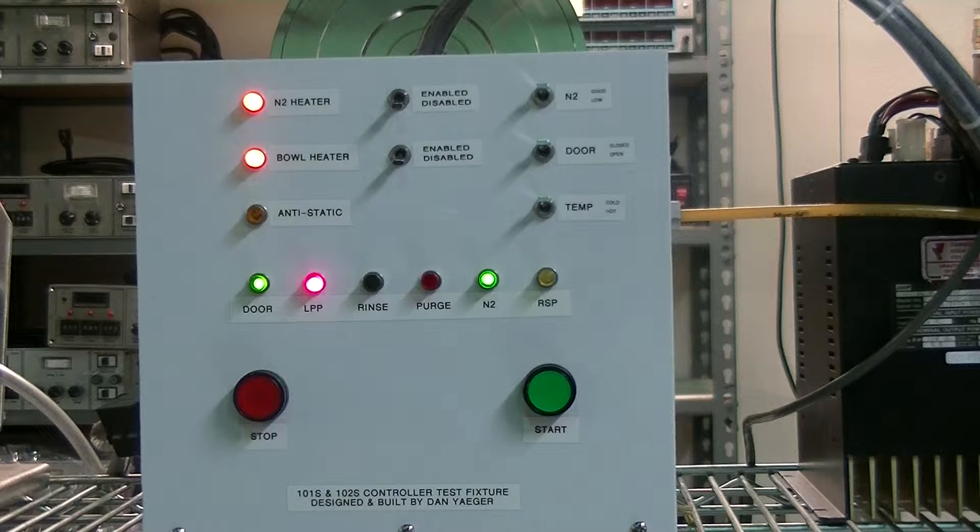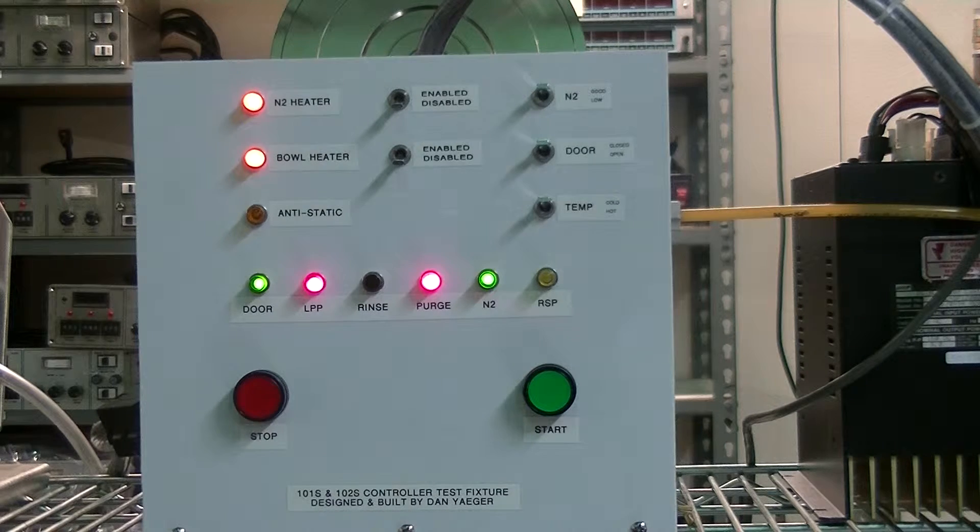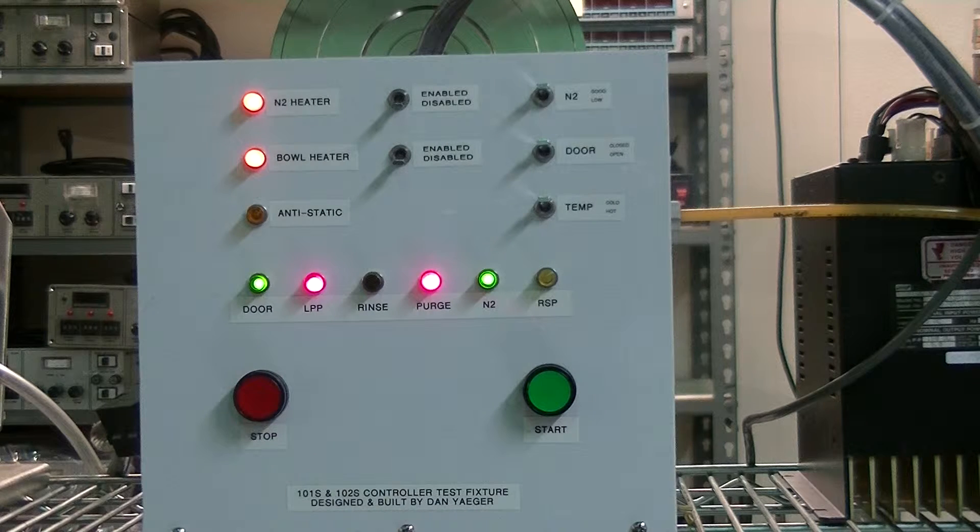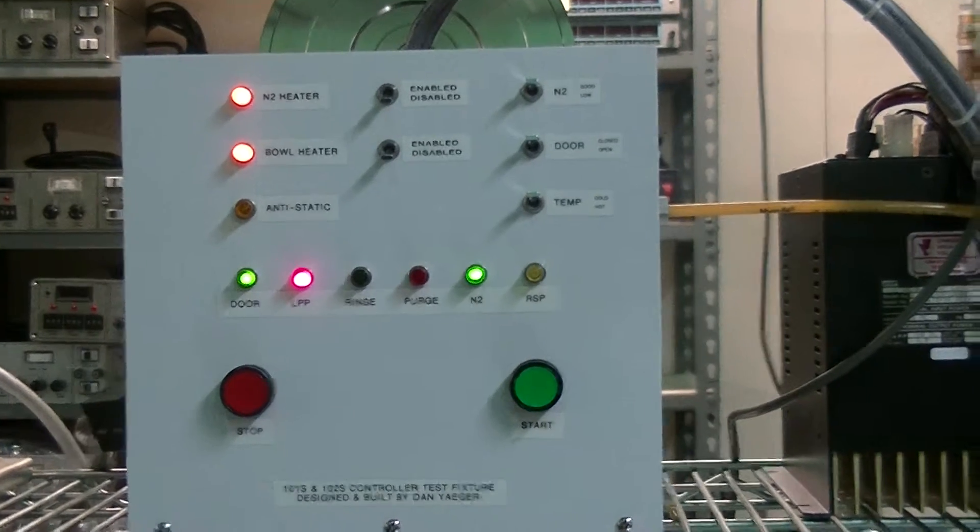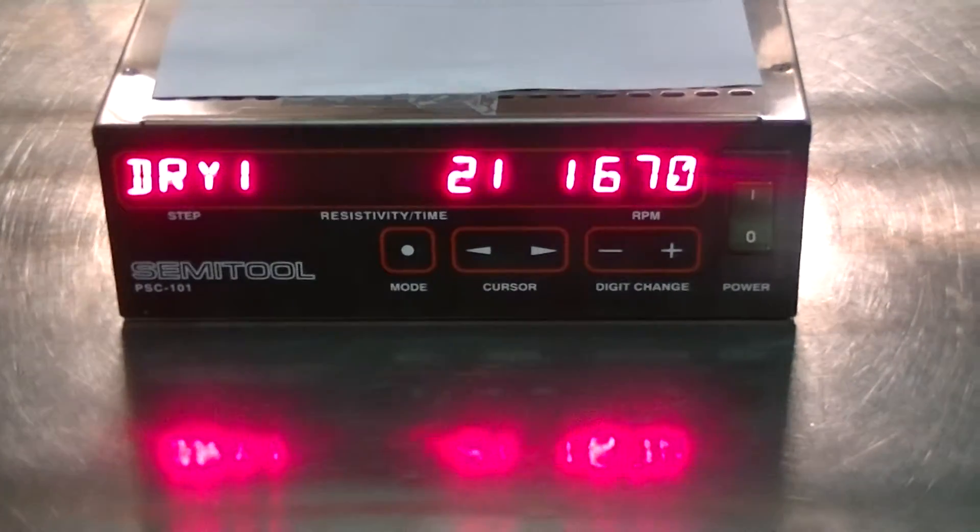All right, now you can see the N2 heater has been enabled. The bowl heater has been enabled. You're going to have your N2 being pressurized and being distributed through the chamber and the purge started to get all of the residual water from the DI lines. And that has shown that we are in dry one here.